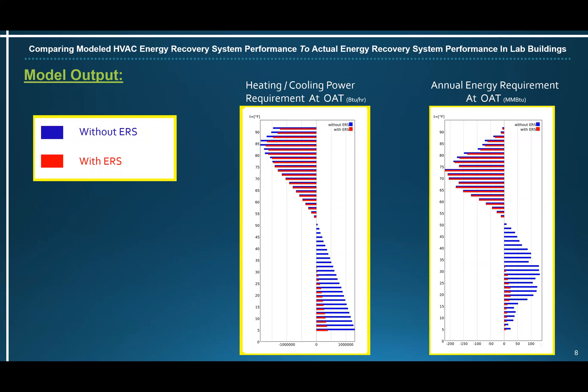Some more model output. The graph on the left shows the heating and cooling power requirement at different outside air temperatures. The x-axis is BTU per hour, and the y-axis is outside air temperature. The blue bar is without energy recovery and the red bar is with energy recovery. The graph on the right shows the annual energy requirement at different outside air temperatures, with the x-axis in million BTUs. You can easily see the reduction in power, peak demand, and annual energy requirement with the energy recovery system.